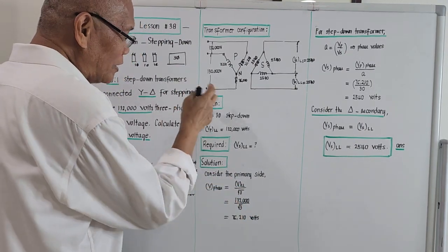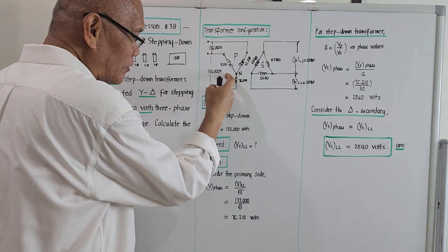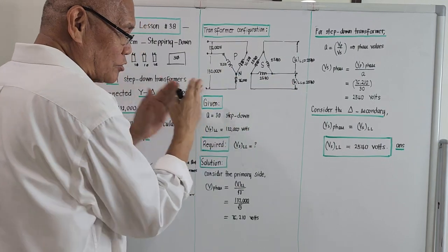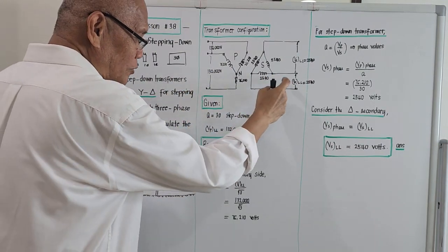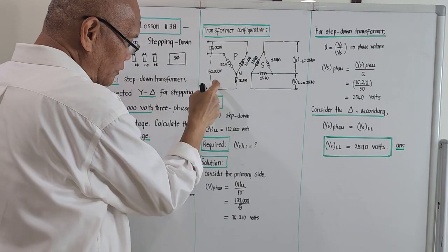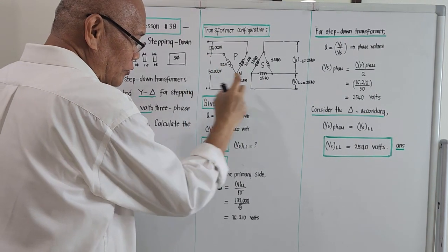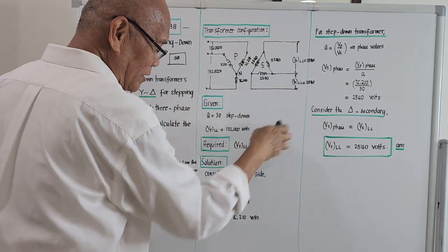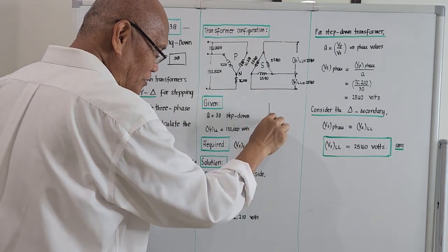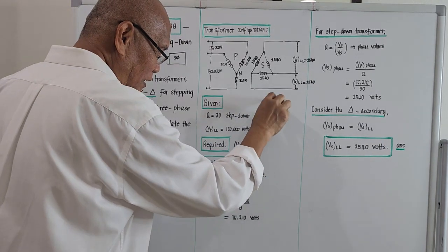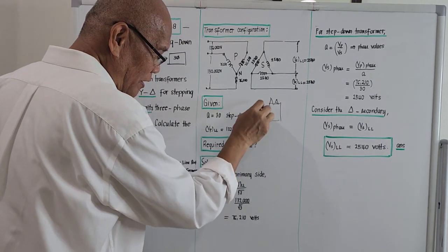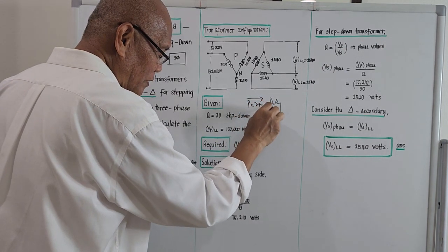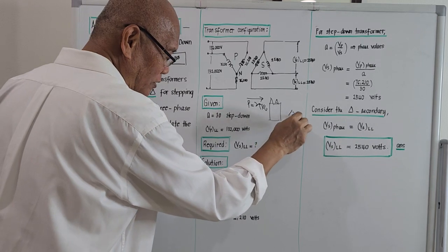Because if we do not convert this 132,000 on the primary, then we make the secondary 120, it's too far. It should be 1,000 volts also. So we will convert this 132,000 to a certain 76,210 voltage. And again, this 76,210 voltage, 2540, upon reaching the secondary post, we'll again have a single phase transformer, in which the primary is 2540 and the secondary will be 120.